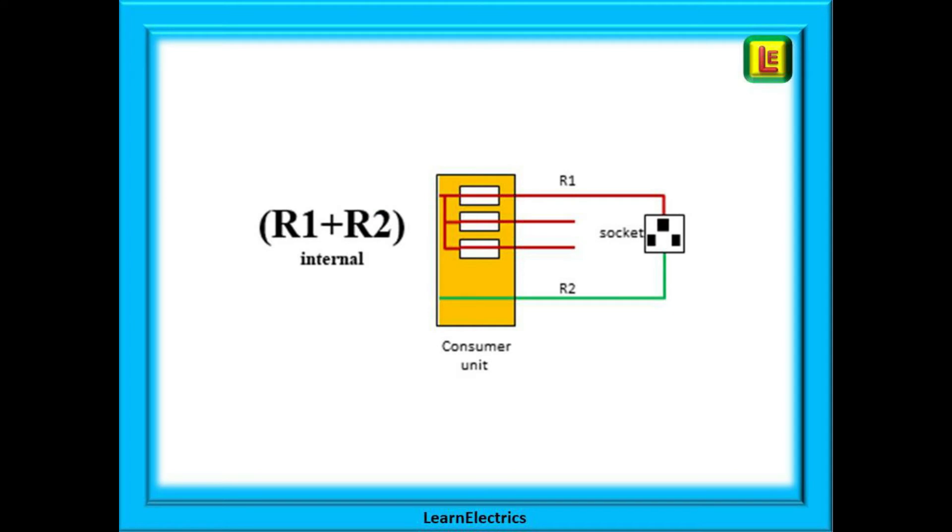Now R1 plus R2 is the inside part of the circuit from the consumer unit to the furthest or most remote part of each circuit in the property. In other words, the longest cable length possible from each fuse or MCB. As it is measured on a dead system, it is a resistance measurement. It is the part of the installation that is under your control, the internal wiring of the phase or live conductor and the earth conductor. R1 plus R2 is the part of the circuit that is inside the property.